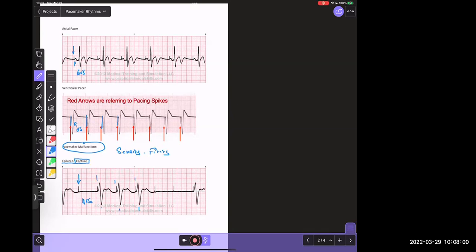So this looks to be ventricular pacing. And then you have a spike here, no QRS, a spike here, no QRS. So you've got these dropped QRSs. These spikes are not producing QRSs, and so you have a failure to capture. And this may be due to many things. Maybe there is a problem with the pulse generator. It is not generating enough amperage. Perhaps it's a battery problem. Maybe there is a problem with the electrode or the probe that is going into the heart or onto the heart. Maybe it is frayed, or there's some problem with conduction through it. But either way, this is what we call a failure to capture situation.